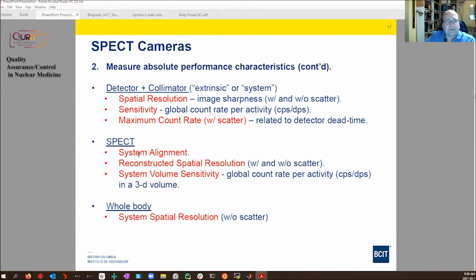Performance characteristics specific to SPECT include things like system alignment and the resolution when we reconstruct point sources. Again, this is analyzing how wide point sources look when they are being reconstructed. This is a very important measurement. It takes a lot of potential issues with calibrations. It can measure the impact of that, and sensitivity. Whole body scanning has another type of system resolution. So this is done in acceptance testing.